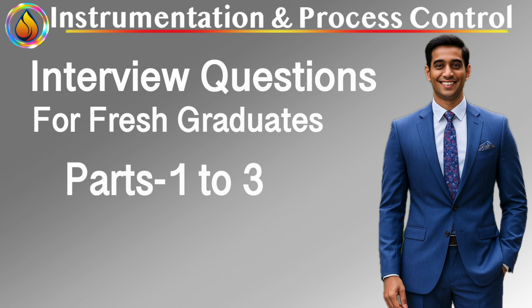What is a 2oo3, 2 out of 3 voting logic, and where is it used? 2oo3 voting is used in safety instrumented systems, SIS, to ensure both reliability and availability. Out of 3 sensors, the logic takes the common result of any 2. It tolerates one sensor failure without triggering a false trip, common in critical trip systems like compressors, furnaces, or reactor shutdowns.